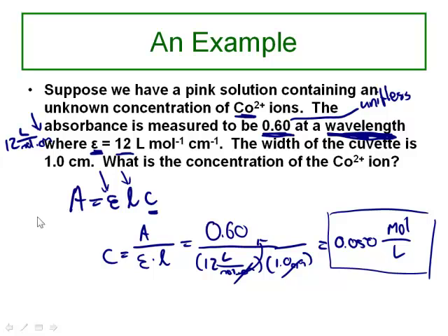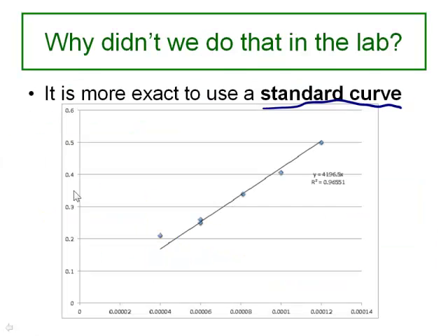If I'm using Beer's Law, the underlying assumption is that if I'm using this for different concentrations, we're assuming that my instrument performs well over the entire range of absorbances, and that's not often true. Oftentimes, a spectrophotometer will not have a linear performance range. What I mean by that is that it will measure the mid-range concentrations, the absorbance, very well, but at low concentrations and at high concentrations, the absorbance becomes pretty inexact. Okay, so it's better to use a standard curve like this.